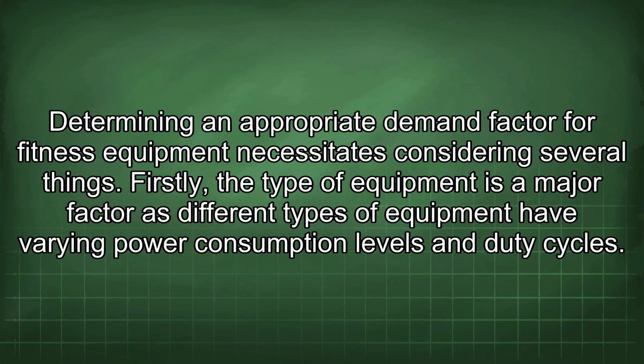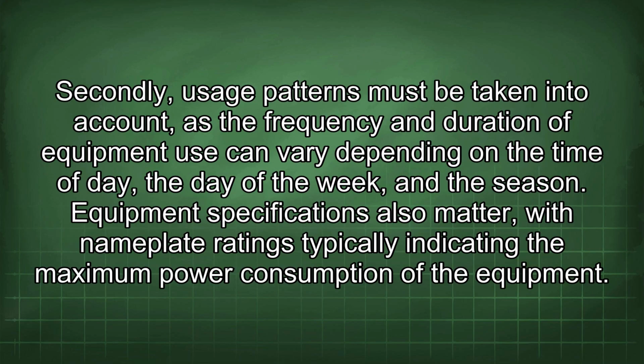Determining an appropriate demand factor for fitness equipment necessitates considering several things. Firstly, the type of equipment is a major factor, as different types of equipment have varying power consumption levels and duty cycles. Secondly, usage patterns must be taken into account, as the frequency and duration of equipment use can vary depending on the time of day, the day of the week, and the season.